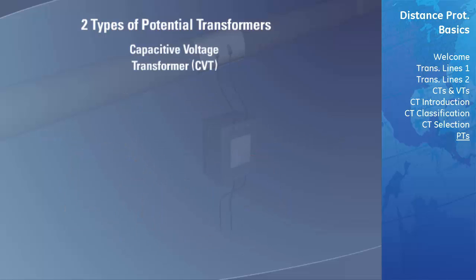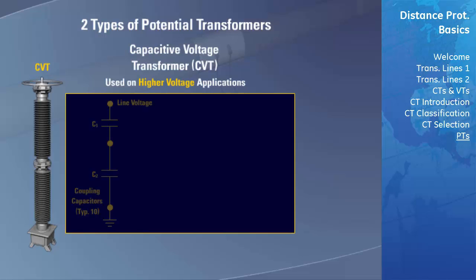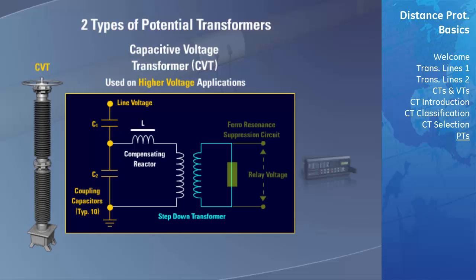Capacitive voltage transformers, or CVTs, are normally used on higher voltage applications. The CVT is basically a capacitance potential divider and consists of the following components: coupling capacitors (typically 10), a compensating reactor, a step-down transformer, and a ferro-resonance suppression circuit found just before the output terminals for connecting to a relay.